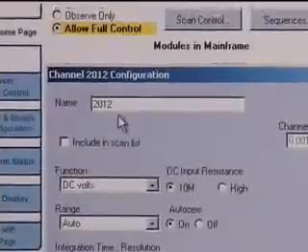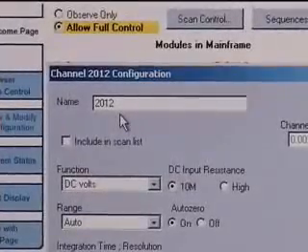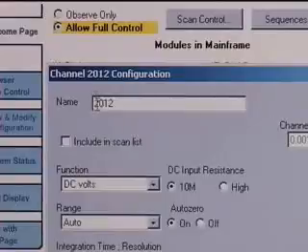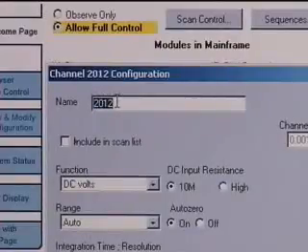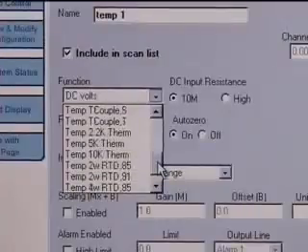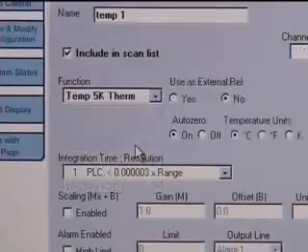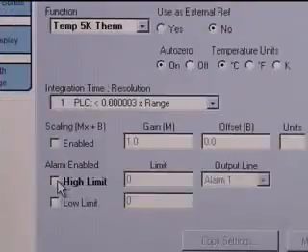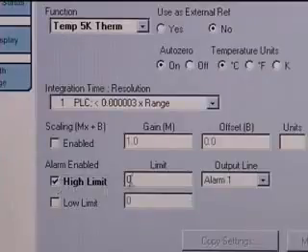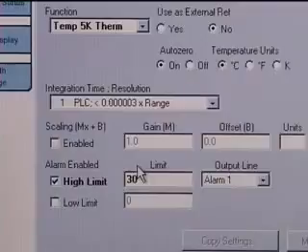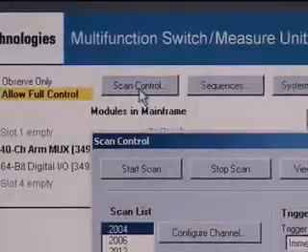Channel numbers are intuitively based on the slot and multiplexer channel. Channel 2012, for example, is the 12th channel in the second slot. Each channel can be assigned a label and configured for temperature sensor or voltage measurements. A limit and an alarm can be programmed for each channel. Once configured, each channel, including its label, can be monitored from the front panel.